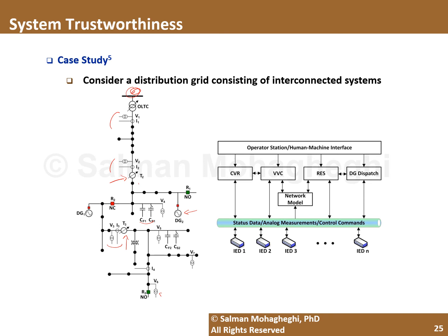And I'm assuming that I'm implementing different functions for this feeder. I'm trying to optimize the dispatch of those DG resources. I'm having an application for electric service restoration if anything happens to this feeder, so we can supply the loads from other alternative sources and alternative routes. We have voltage VAR control in order to regulate the shunt capacitors and voltage regulators, and also I have conservation voltage reduction, in which I try to lower the node voltages in order to reduce the demand.